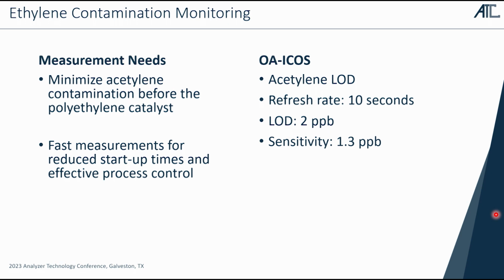Why is this important? Minimizing the amount of acetylene helps preserve a catalyst downstream. As the ethylene shifts downstream for further production, it's a catalytic reaction. The acetylene is a poison. So they want to get it as low as possible, and they want to maintain it. If the acetylene spikes, they want a quick response to divert that, either to put it back through, or to flare it, or to store it, I don't know, whatever the engineers do. And the other really important thing here is that minimizing acetylene has a significant impact on startup time. The faster you can measure it, the quicker you can start up a unit following a shutdown.